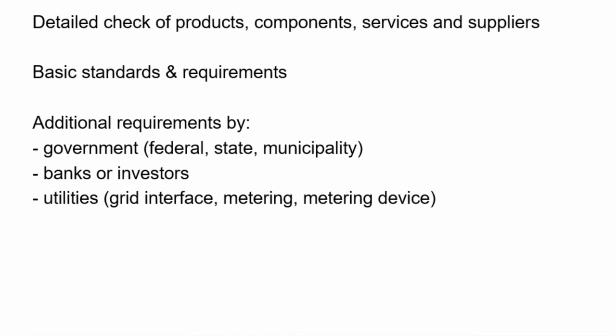Now we come to the detailed design phase — a detailed check of products, components, services, and suppliers. We have first basic standards — for example, the module has to be certified to IEC 61215 — or additional requirements, such as PID resistance, ammonia resistance if there's a farm nearby, or salt mist resistance if you're at the seashore. You have to choose an adequate norm and make it part of the contracts with the supplier.